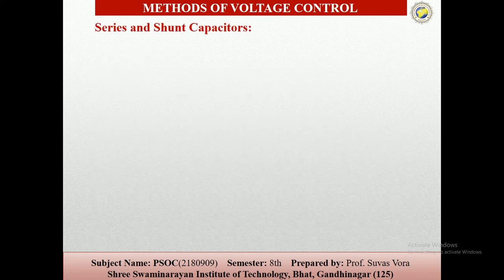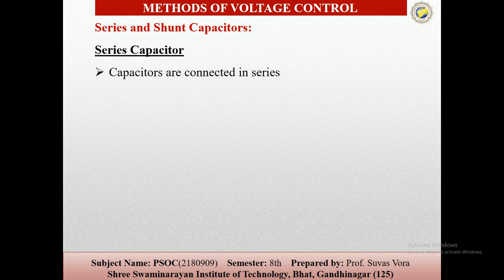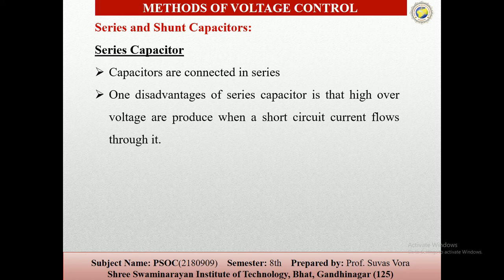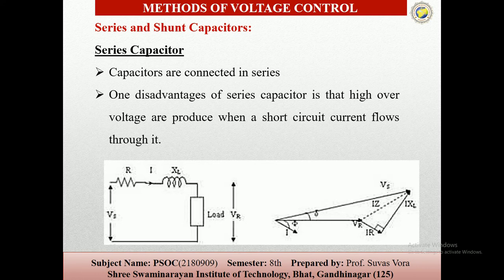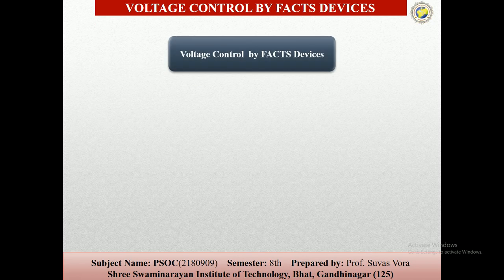Then after that, the series capacitors. As we know, the capacitors are connected in series with the transmission line conductors, and they are used to reduce the inductive reactance between the supply point and the load. One disadvantage of the series capacitor is that high voltage is produced when the short circuit current flows through it. So these are the phasor diagrams with the connections of the series capacitors. Now the next one is the voltage control FACTS devices.